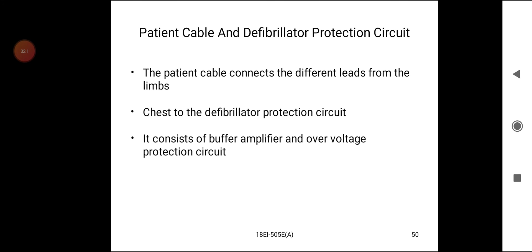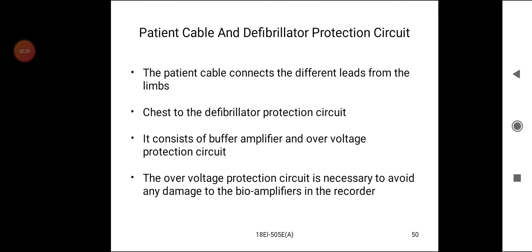Patient cable and defibrillator protection circuit. The patient cable connects the different leads from the limbs and chest to the defibrillator protection circuit. It consists of a buffer amplifier and over voltage protection circuit. The over voltage protection circuit is necessary to avoid any damage to the bioamplifiers in the recorder.